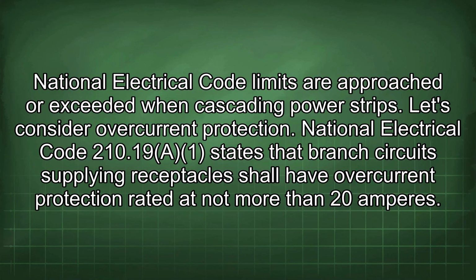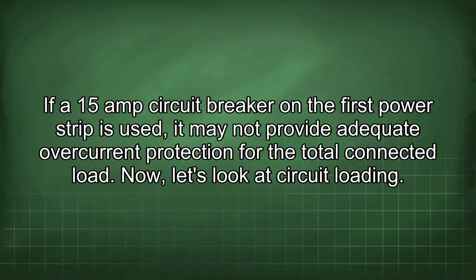National Electrical Code limits are approached or exceeded when cascading power strips. Let's consider overcurrent protection. National Electrical Code 210.19 states that branch circuits supplying receptacles shall have overcurrent protection rated at not more than 20 amperes. If a 15 amp circuit breaker on the first power strip is used, it may not provide adequate overcurrent protection for the total connected load.